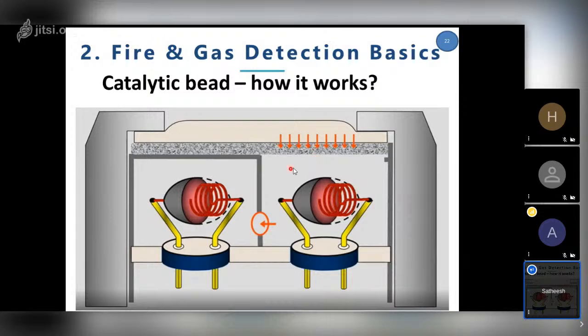Now, this technology is quite old and it has its own limitations. For example, if any sticky gas comes, the bead will be coated and the bead will be dead. You cannot detect any more gas. So this is not a very reliable technology. It's old technology. We don't use it for all flammable gases, but there is one application where only catalytic bead can be used, with no other technology available. That is for hydrogen detection. Hydrogen is a flammable gas again, but not a hydrocarbon. There is only the H, hydrogen molecule.